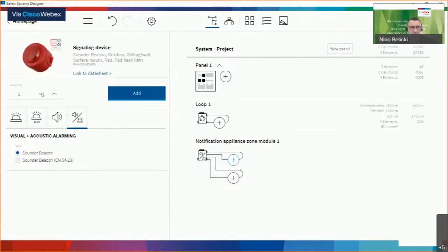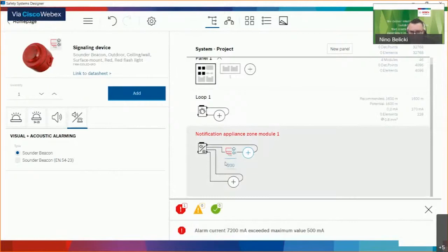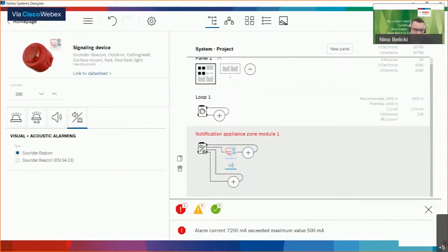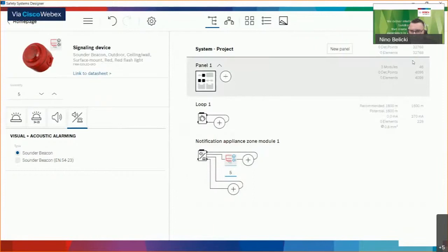If I try to do something that is not technically possible, in the lower part we always get information about it — it could be an overload due to lack of power, system limits, or other technical limits. On the right side, you can always see what the maximum is for that unit at the system level, panel level, and module level. The column second from the right shows what is actually in the system.